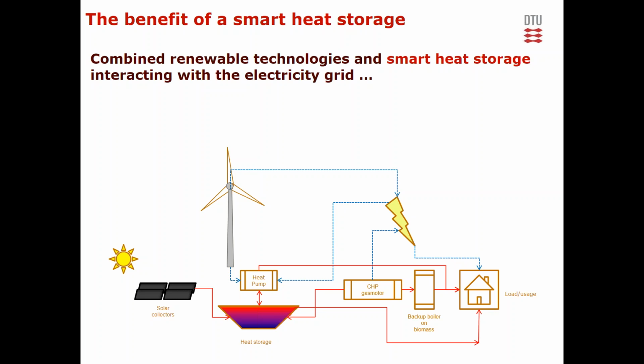When there's a very low electricity price, it's not economical for the plant to produce electricity, so the generator can be shut down and heat taken from the storage to supply the consumers. When the electricity price is high, heat or waste heat can be generated by the CHP generator and stored. In periods of low electricity price, the heat pump can also be activated to boost the lower temperature in the storage and use it directly for heating the network.